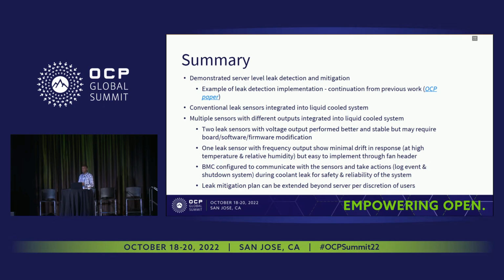And again, on the mitigation, as I mentioned, we left the mitigation plan beyond the server to the discretion of the customer. If it is scaled up to include the rack or multiple racks, let's say an end-of-row CDU supported multi-rack system, and you want to integrate all that, the mitigation plan might be different. Instead of just shutting down the individual systems, you might even consider controlling the CDU, or you put a valve somewhere in the manifold and operate the valve, stopping the flow to that affected or leaking server. So that's all left to the discretion of the user.